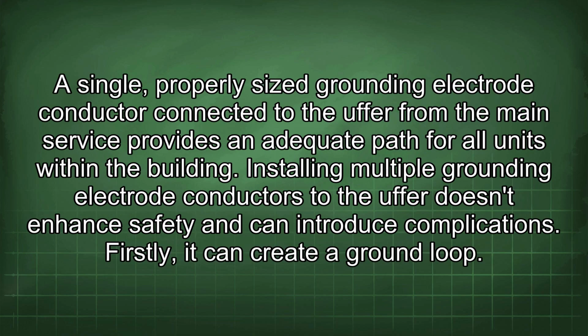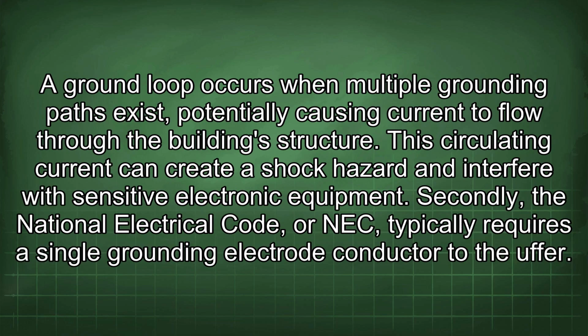A single, properly sized grounding electrode conductor connected to the Ufer from the main service provides an adequate path for all units within the building. Installing multiple grounding electrode conductors to the Ufer doesn't enhance safety and can introduce complications. Firstly, it can create a ground loop. A ground loop occurs when multiple grounding paths exist, potentially causing current to flow through the building's structure. This circulating current can create a shock hazard and interfere with sensitive electronic equipment.